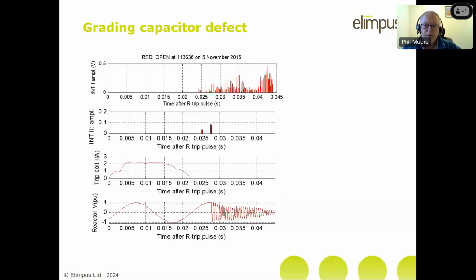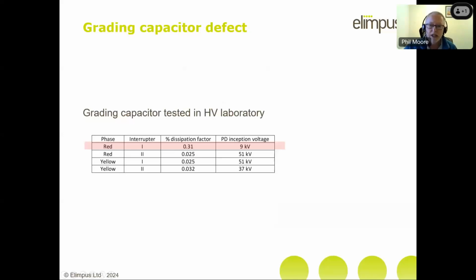So we reported this, and the utility were very kind enough to actually investigate this for us. What they did is, I think this is on the red phase, they took off all the red phase capacitors, and they also took off the yellow phase because that was the phase next to it, in case we hadn't quite got it right. And they took them to an HV laboratory and tested them all. They tested for the inception of PD, which you need an HV lab to do. It's very difficult to do it anywhere else.